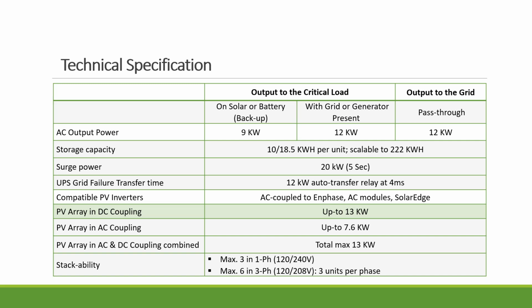Now the grid transfer time is very quick. So that means if the grid goes off, the hybrid inverter will start, create an island system, disconnect from the grid, and bring on power within 4 milliseconds. Very, very quick. It basically meets the UPS (uninterruptible power supply) standard, which typically requires less than 10 milliseconds.